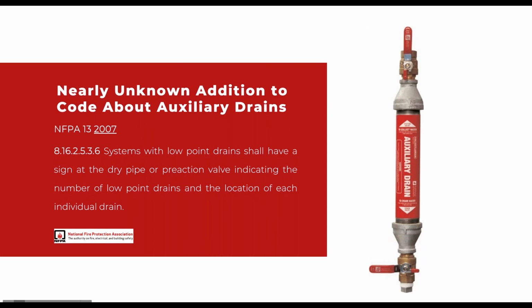And that's really what we saw in the Texas problem. You had just dozens and dozens of systems in buildings that had traditionally not been subjected to freezing temperatures, so they were surprised by that. And you had an issue where no one had gone around and checked the low point drains to get out any accumulated moisture. And sometimes they didn't even know that they had these low point drains in the building.